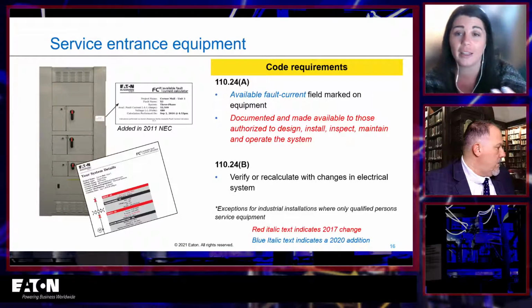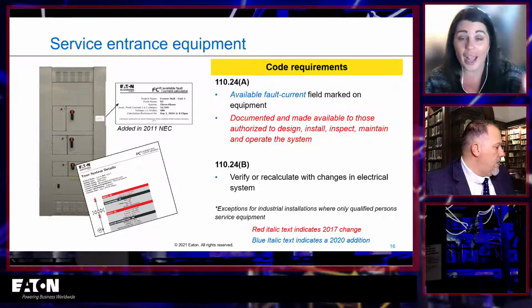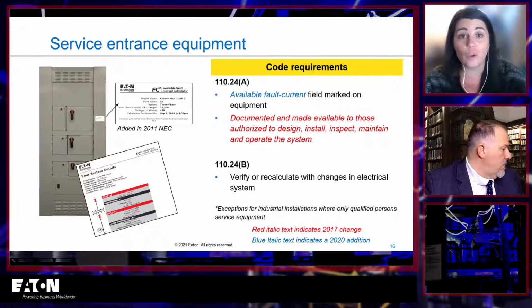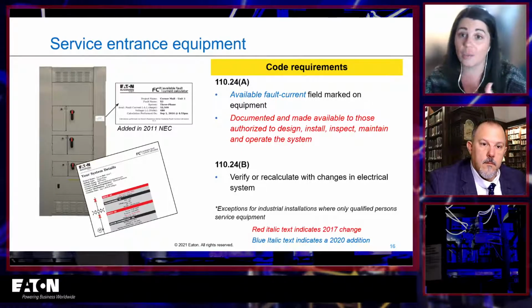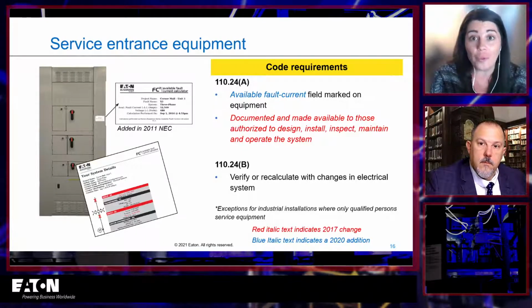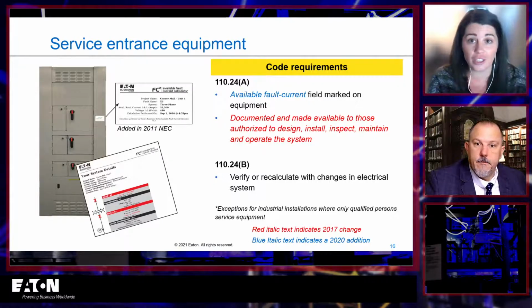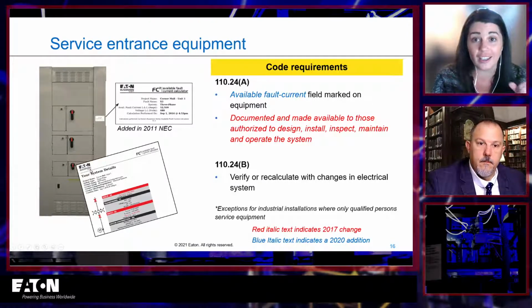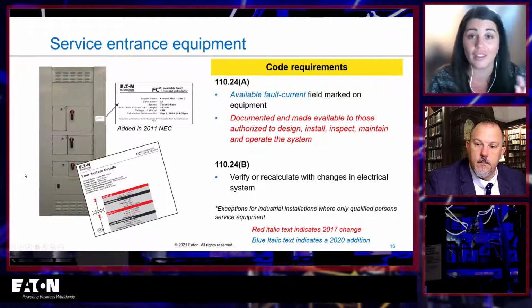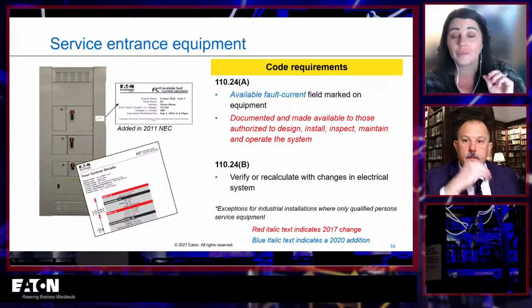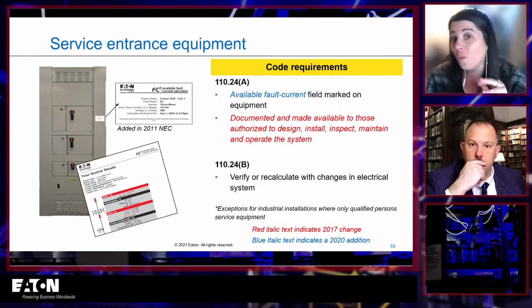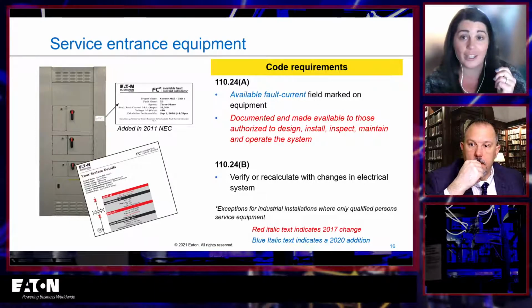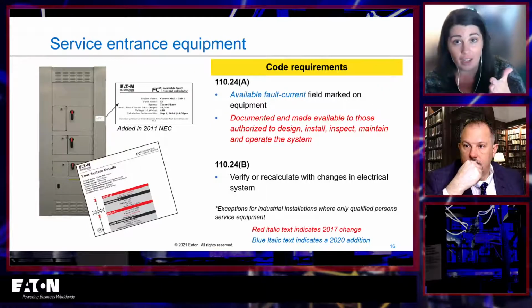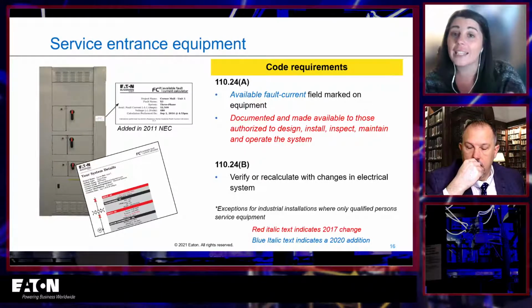Available fault current is a little more complicated than that. So in order to know that your ratings are adequate for the available fault current, and to enforce that they're not being installed somewhere they shouldn't be, you have to know what the available fault current is. So all of these changes aren't necessarily changes in, hey, SCCR is important and it should be greater than the available fault current. It's so important. We know you might not know what the available fault current is, but you have to now, and you have to verify that the equipment being installed has adequate ratings for that available fault current.